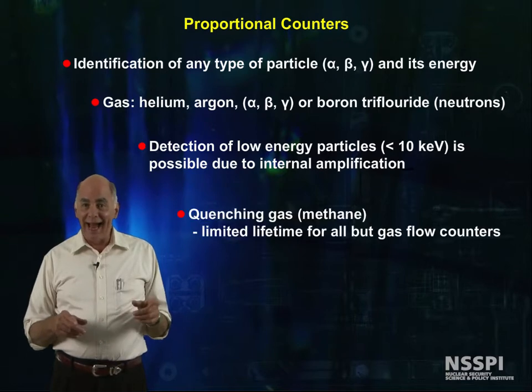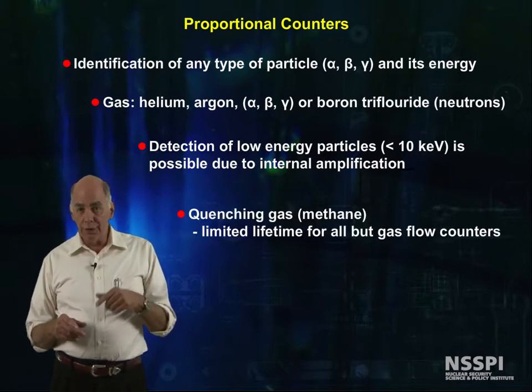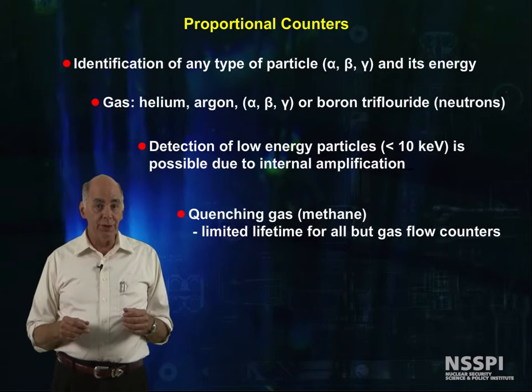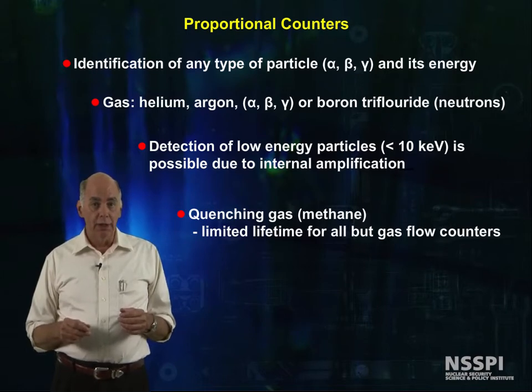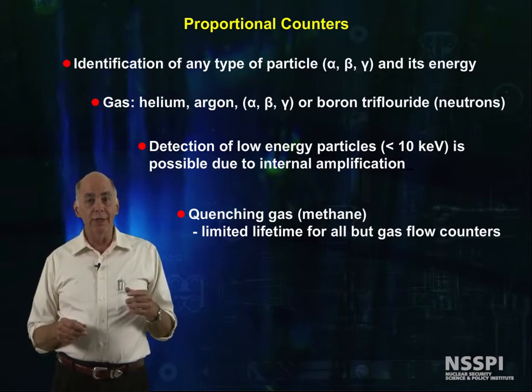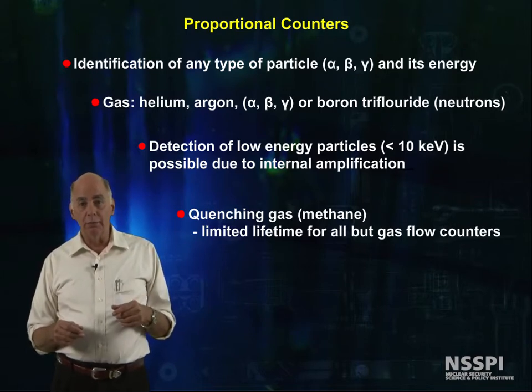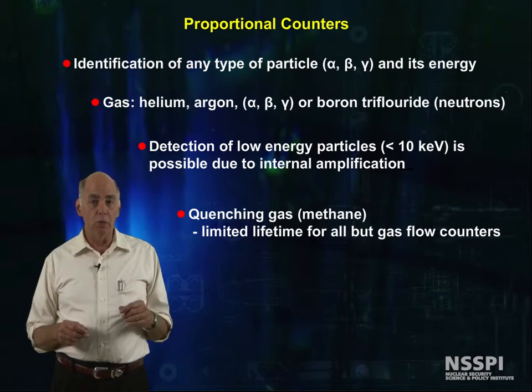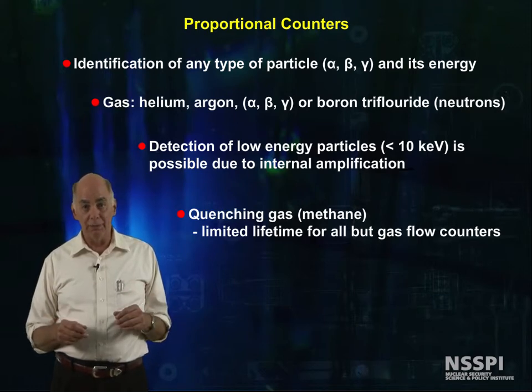To stop a Geiger-Mueller discharge, a quenching gas, often methane, is added to the counting gas. This helps resolution, but limits the lifetime of proportional counters for all except gas flow counters.